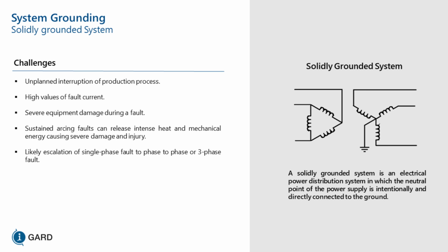Solidly grounded systems. So you can see here that in the solidly grounded system, you have 3-phase conductors, with the midpoint of all those coils connected to ground with no intentional impedance between them. When you have a ground fault, remember, a phase touches ground, you use the bonding network of your entire facility to get back to that ground point that's going to connect to the neutral, and you complete the circuit. So a ground fault just basically completes the circuit. But because you have no intentional impedance, you have a tremendous amount of current flowing.